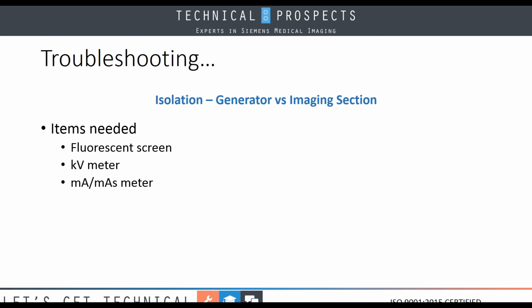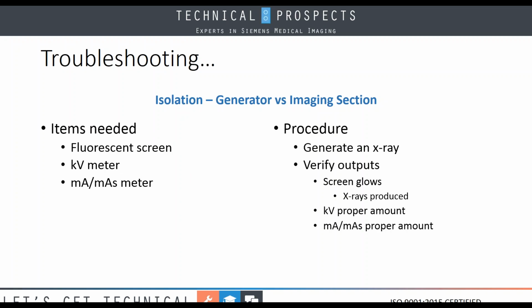A couple of devices that I think can make this easy for you: take a fluorescent screen. Now, if you don't have an old cassette laying around, if you do, just cut it out of there, because all we need it to do is just glow. Get your kV meter and get your mA and mAs meter. And if need be, you can add your dose meter into this as well. What I want you to do is to generate an X-ray. Look at the outputs. Does your screen glow? It means you're making X-rays. Check your kV. If it's at the proper amount, we're good to go. If mA and mAs is proper, again, we're good to go. If dose is good, your generator's fine. Now our problem's on the imaging side of the house. Look at what we just did. In one quick X-ray, we can determine which side of the house our problem is on.